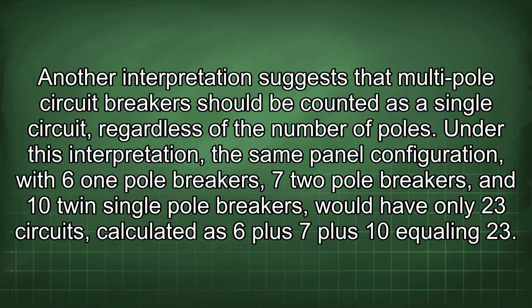Another interpretation suggests that multi-pole circuit breakers should be counted as a single circuit, regardless of the number of poles. Under this interpretation, the same panel configuration, with 6 one-pole breakers, 7 two-pole breakers, and 10 twin single-pole breakers, would have only 23 circuits, calculated as 6 plus 7 plus 10 equaling 23.